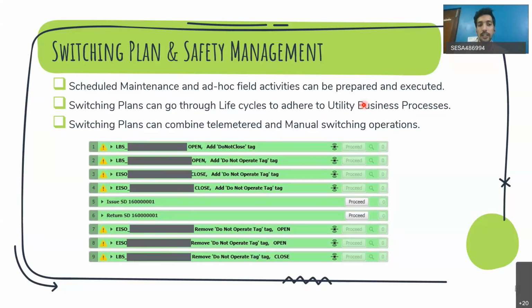These switching plans can combine telemetered and manual switching operations. For example, a particular load break switch is opened, another load break switch is opened, and an earth switch is closed. This way, a section is isolated and earthed, then the actual maintenance activity is carried out, then the reverse happens.